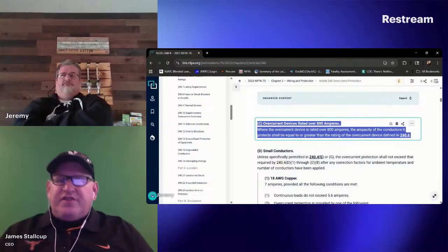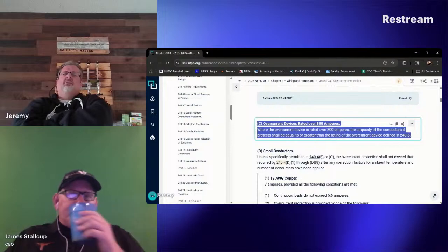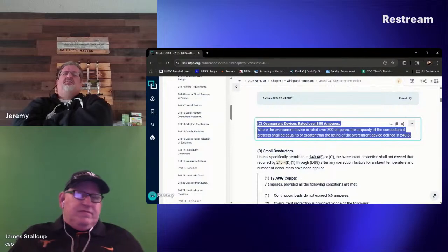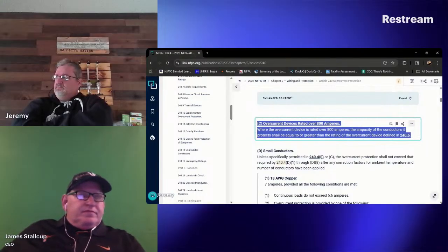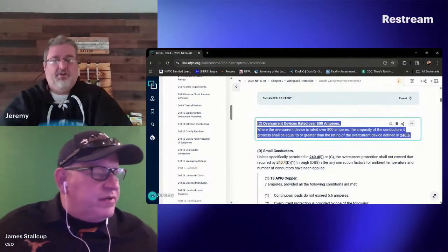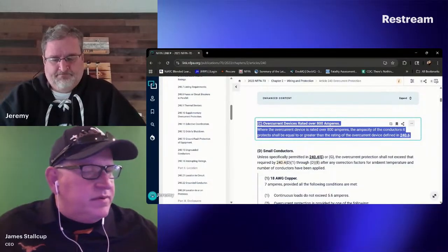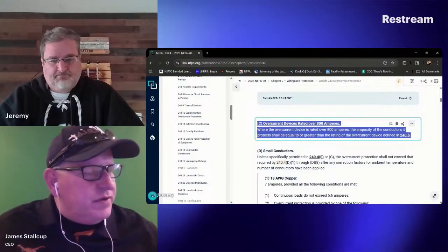You've got diversity there. Okay, so take that 700 and what was it? 24 amps of continuous load. Add 600 amps of non-continuous load to that. What would you get? You had 724, and you were continuous. 724 times 125%.